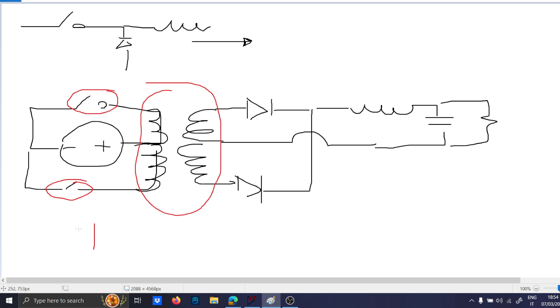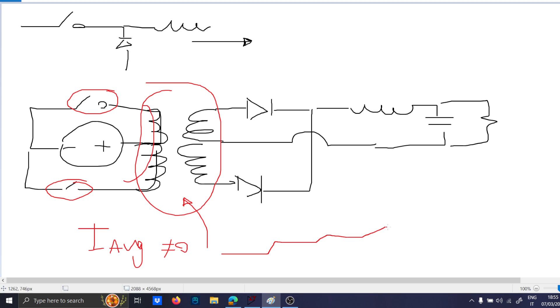And having a non-neutral polarity here means that you have an average current flowing into the transformer which is not zero. And this will lead basically to the saturation of the core of your transformer.